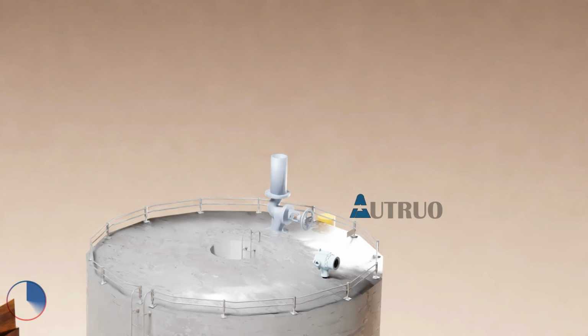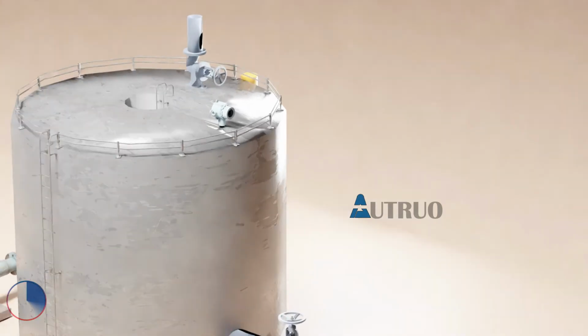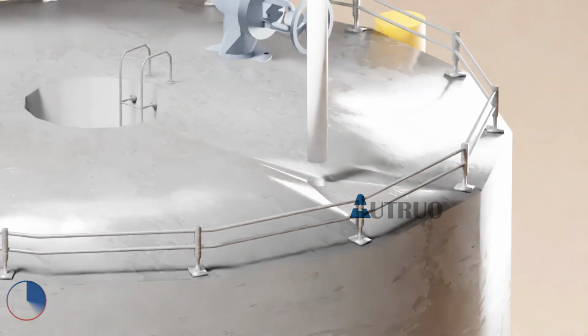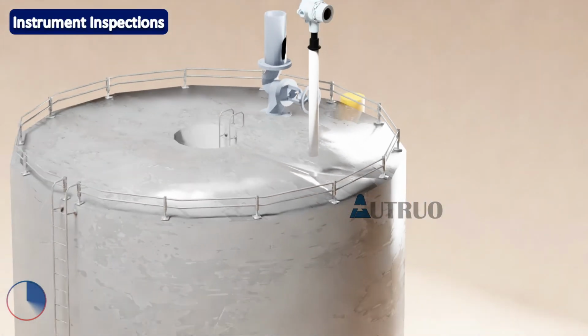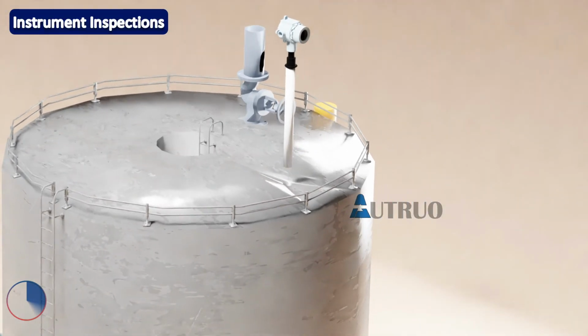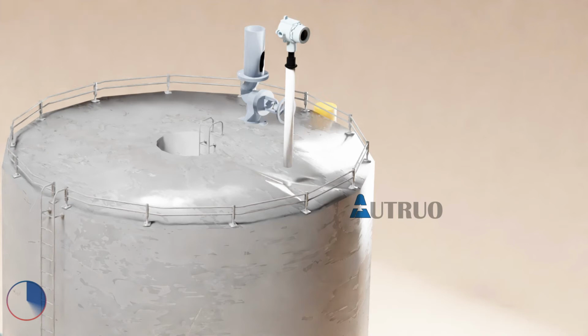Now that there is no fluid pressure within, we will remove the sensor and inspect the tip. From all indications, the sensing tip is free from mechanical damage. Now let's look at the current state of the capacitive level transmitter, which is in terms of the generated current signals at various fluid levels.